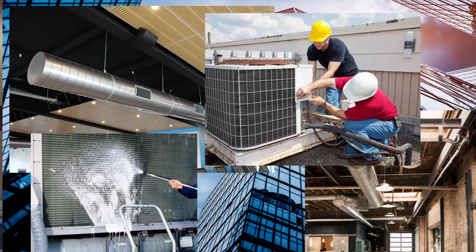Tommy, what do you think? Although the air conditioning systems are unlikely to contain active virus, it's highly recommended that the key components of the HVAC system be visually assessed for the internal conditions and documented with the focus on the air handlers and the outlying VAV boxes. Systems that have been dormant for weeks could have other issues such as strong odors from mold, mildew, and bacteria, and those odors can also cause concern with employees inside the facility. These assessments are very low cost and establish a long-term and a short-term plan for the customer and the client to move the air conditioning system forward.